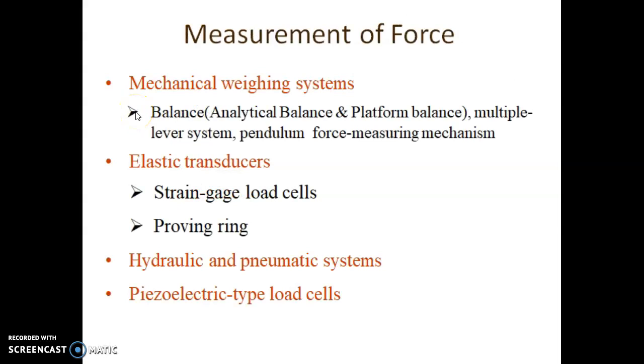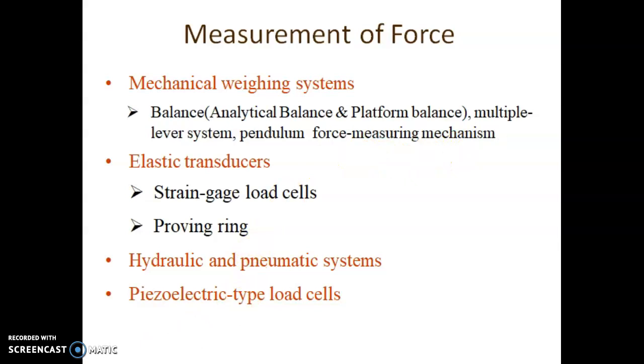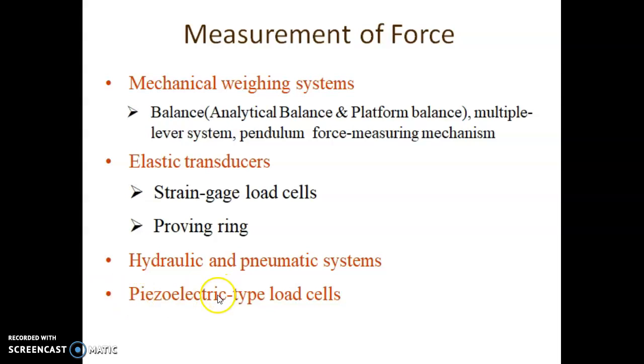Generally, the mechanical weighing systems such as balance — both analytical balance and platform balance — then multiple lever systems and pendulum force measuring mechanisms, are coming under the direct method. On the other hand, elastic transducers such as strain gauge load cells, proving ring, hydraulic and pneumatic systems, and piezoelectric type load cells are coming under the indirect method.